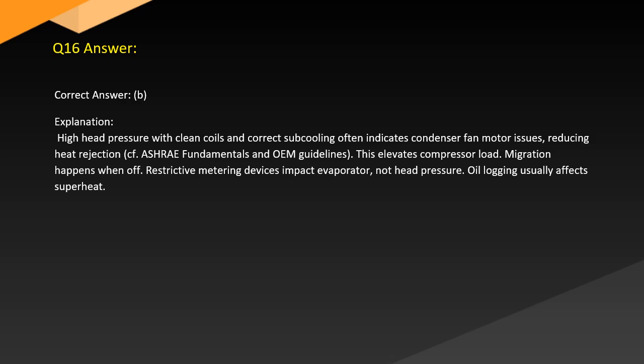Answer. Correct answer: B. Explanation. High head pressure with clean coils and correct subcooling often indicates condenser fan motor issues, reducing heat rejection. CF, ASHRAE Fundamentals and OEM guidelines. This elevates compressor load. Migration happens when off. Restrictive metering devices impact the evaporator, not head pressure. Oil logging usually affects superheat.